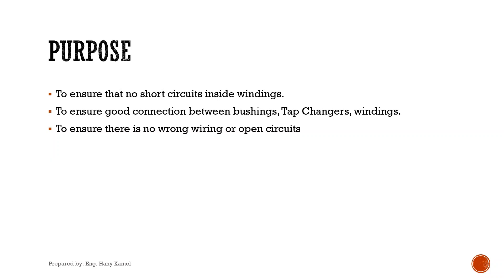Why this test? Winding static DC resistance helps to ensure the following points: no short circuits inside windings, good connection between bushings, tap changers, and windings, and there is no wrong wiring or open circuits.